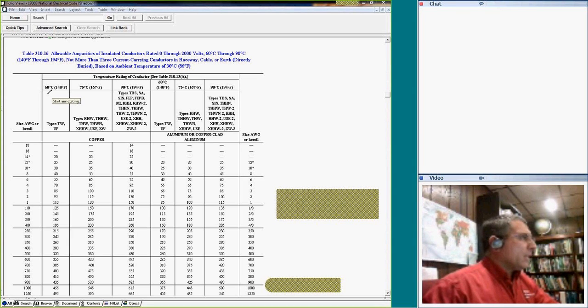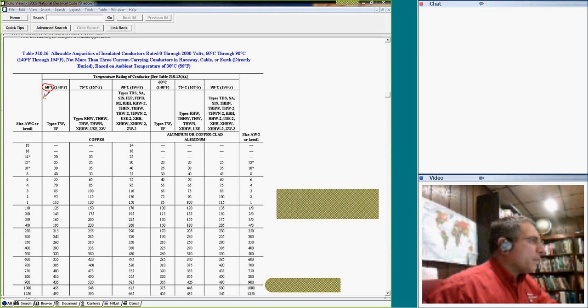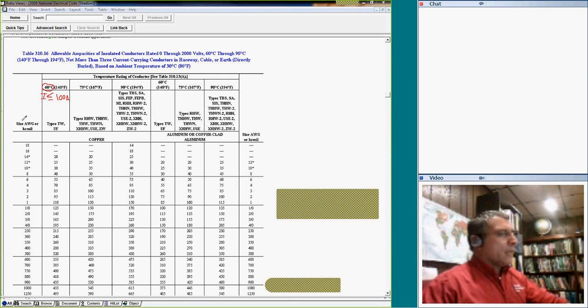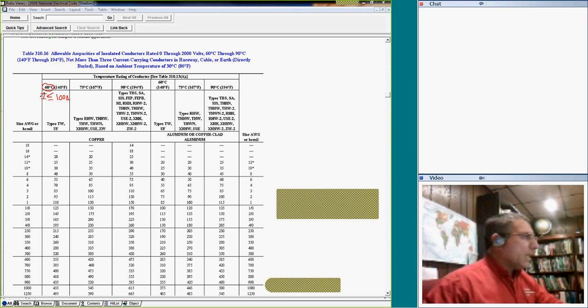I'm going to write a few things, guys, for you here, and I hope you will listen to me. First of all, I want to start with the 60-degree column. Here's where you use the 60-degree column. Number one, guys, if you don't know anything, if the amp is equal or less than 100 amps, you always default to the 60-degree column. No question asked. Conductors 100 amps or less.